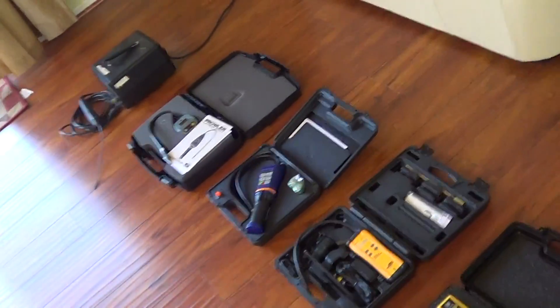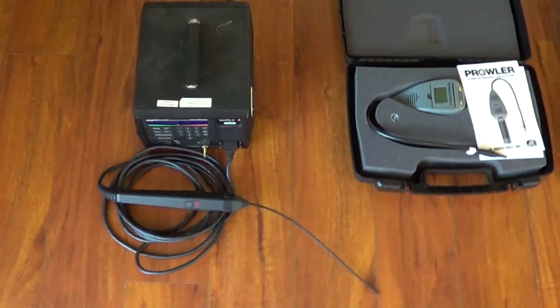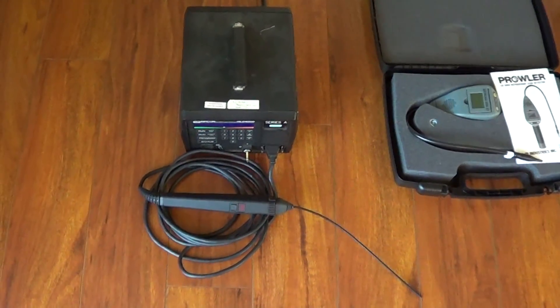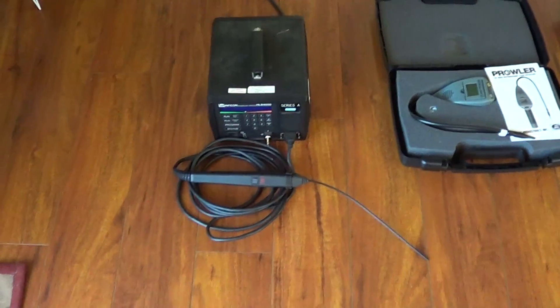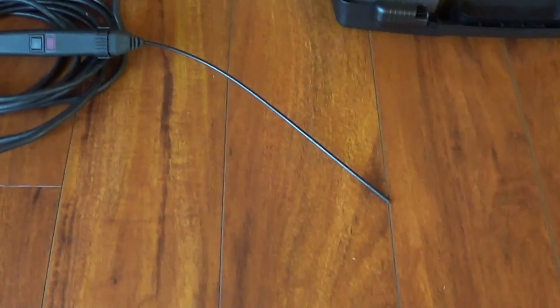As you would imagine, if you spend $8,000 — actually you can get these for about $1,500 used — you will find your R410 leaks with this one. But it's just a pain: it's five minutes to power on, it's very heavy, and the probe can suck up water easily. It's designed to be used in a factory environment.